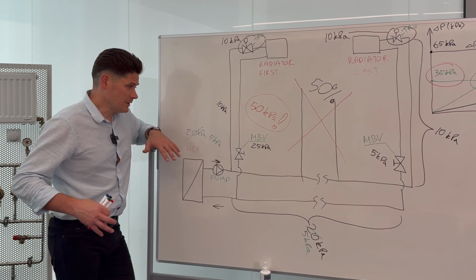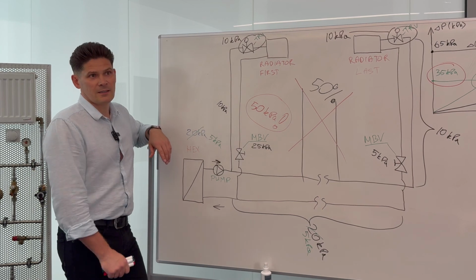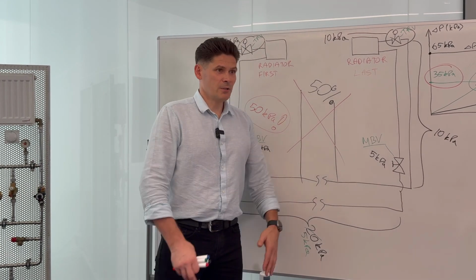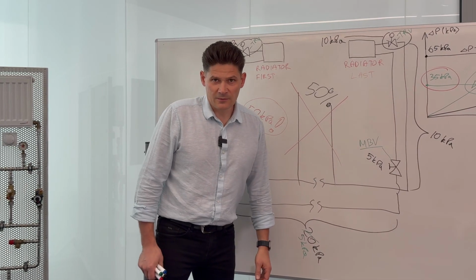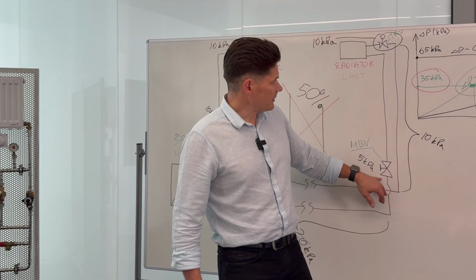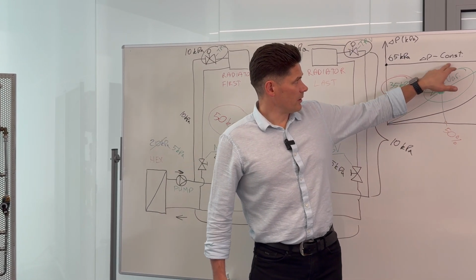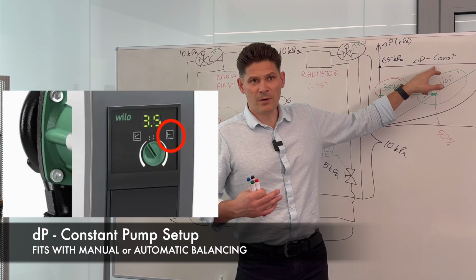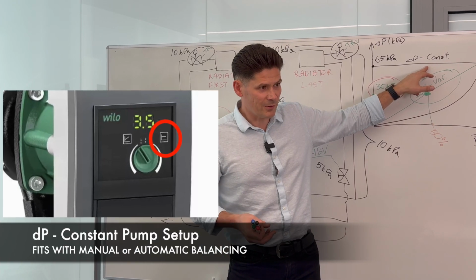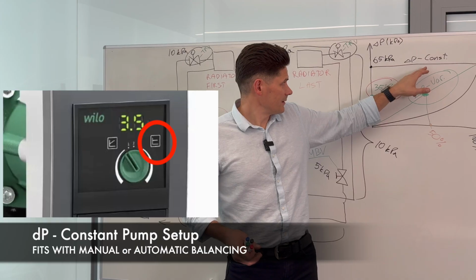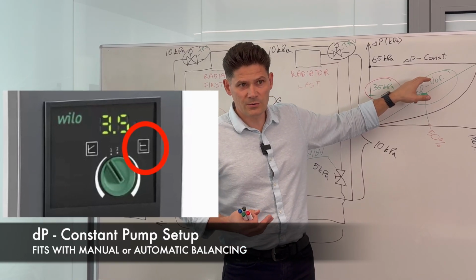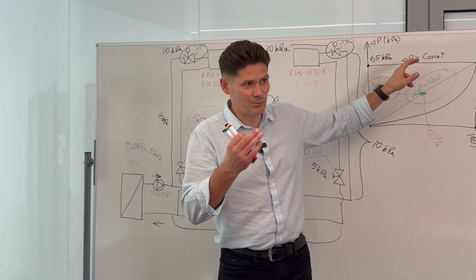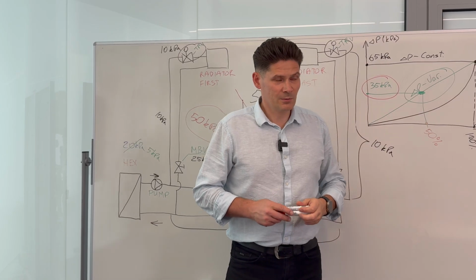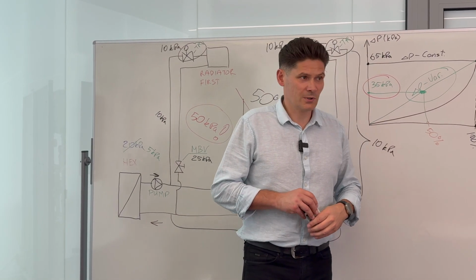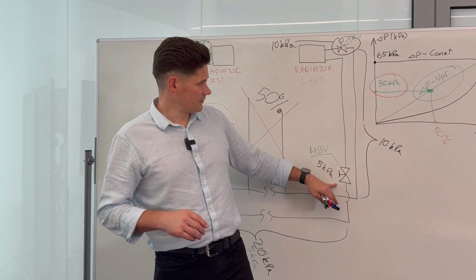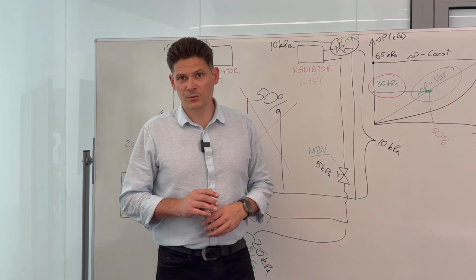So this means I am limited if, for example, these days I'm building a commercial building or a multifamily building with manual balancing valves. This means I am limited to delta P constant regulation. So this means my pump is programmed from the beginning to have, let's say, more energy use, of course more CO2, and I will simply be spending more money just because I am limited. I used manual balancing valves in a system where I should use automatic ones.